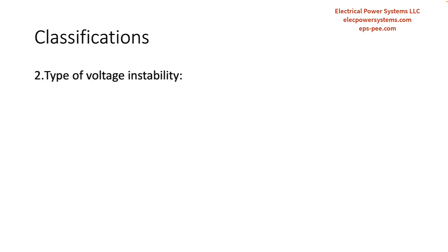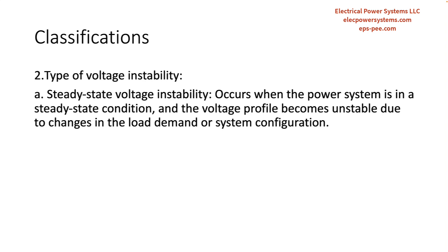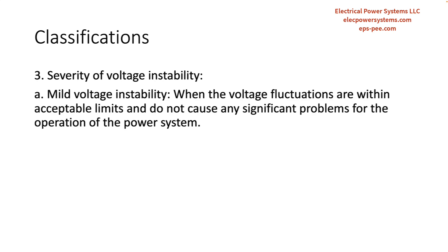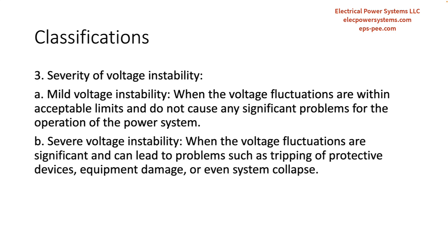Regarding the type of voltage instability: steady-state voltage instability occurs when the power system is in a steady state condition and the voltage profile becomes unstable due to changes in load demand or system configuration. Dynamic voltage instability occurs when there are rapid changes in the power system, such as during a fault or sudden changes in load demand, which can cause voltage fluctuations. In terms of severity, mild voltage instability is when the voltage fluctuations are within acceptable limits and do not cause significant problems, while severe voltage instability is when the fluctuations can lead to tripping of protective devices, equipment damage, or even system collapse.